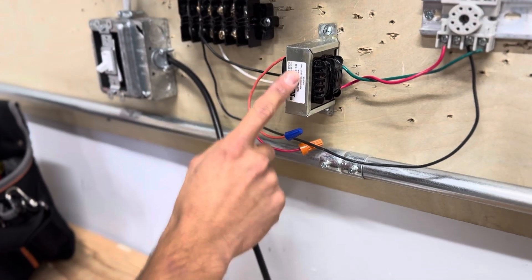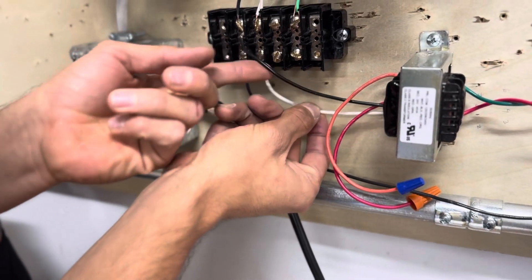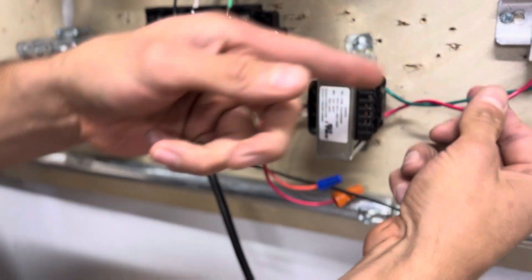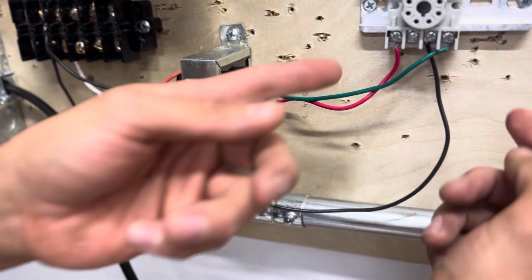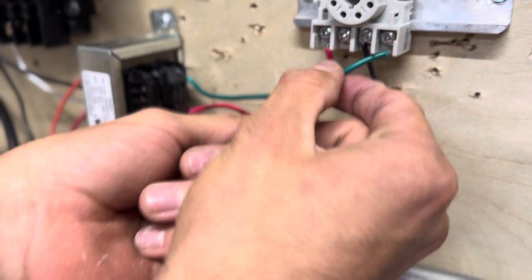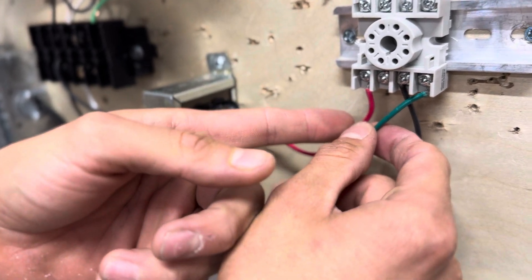It comes from this step down transformer. So we have to feed in a line and a neutral here in order to step down that voltage and make that 24 volts. Now these are your pins 2 and 7 here for the coil. Now order does not matter for the coil meaning the polarity can be reversed.